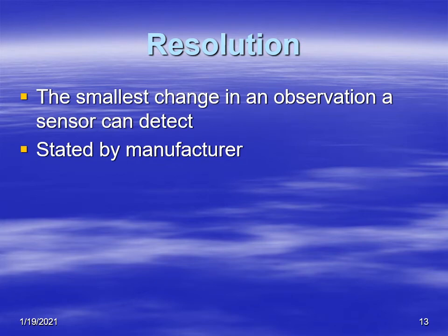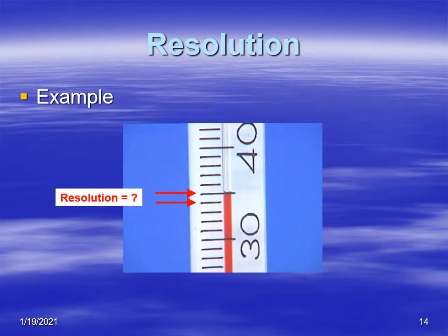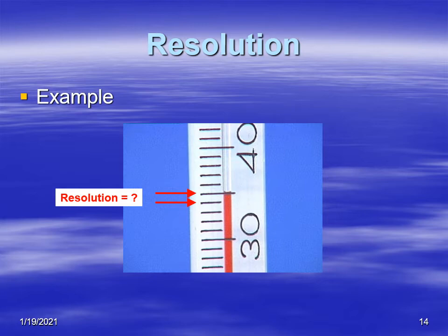Resolution is the smallest change that an observation or a sensor can detect. Usually this is stated by the manufacturer and is indicated by the markings on the scale. If it's a digital readout, that's a little more difficult and you'll have to go into the manual to find the resolution. In this case it would probably be a resolution of maybe one degree Celsius unless the manufacturer tells you something different.